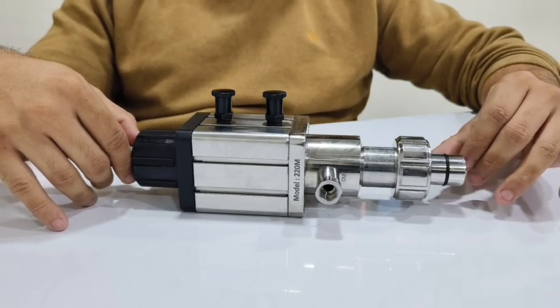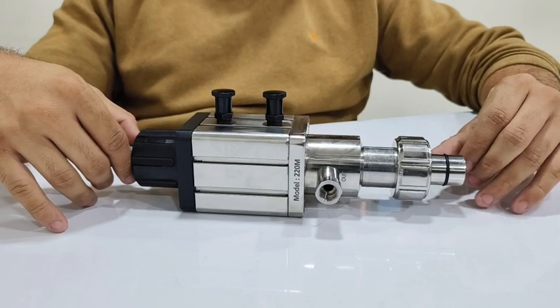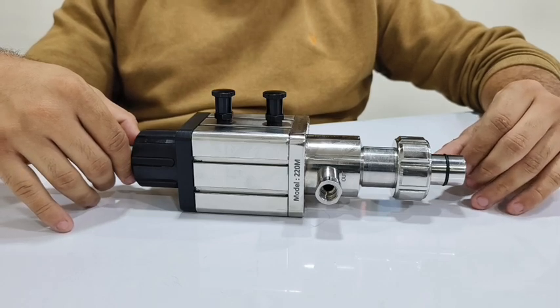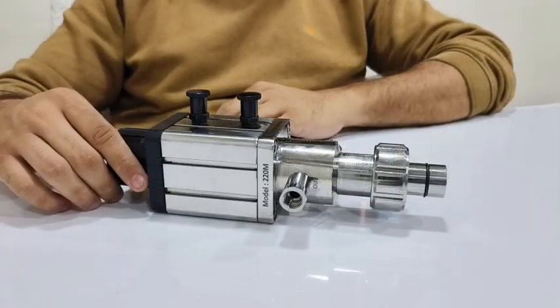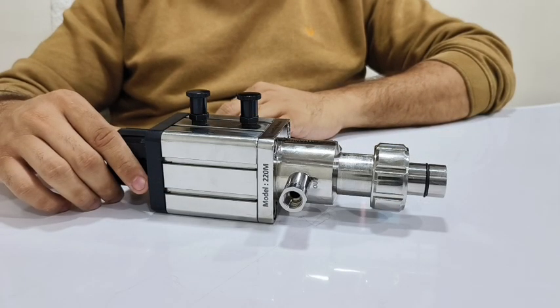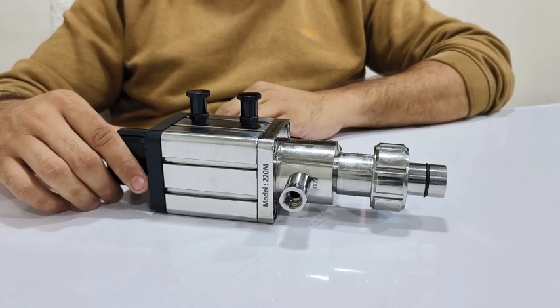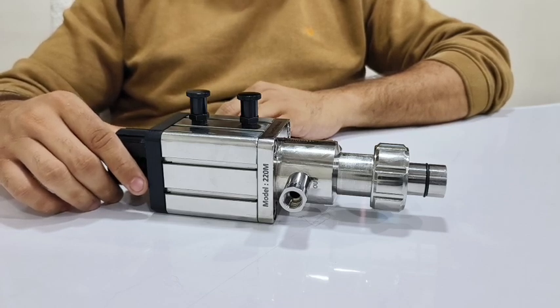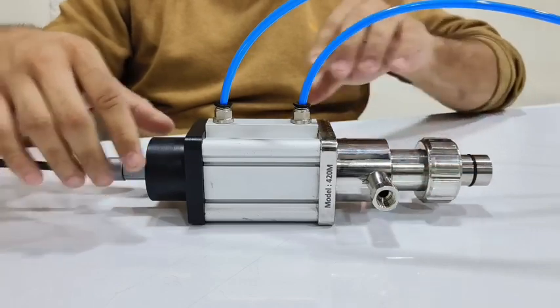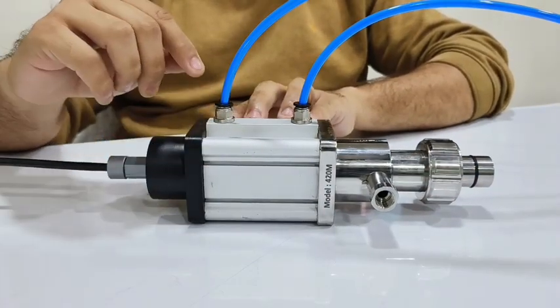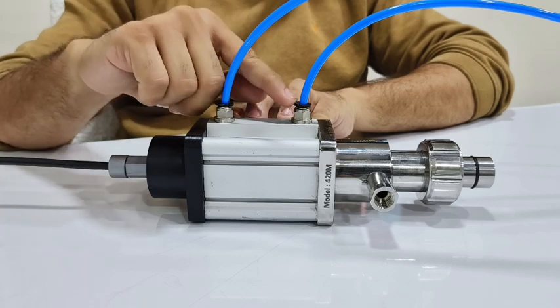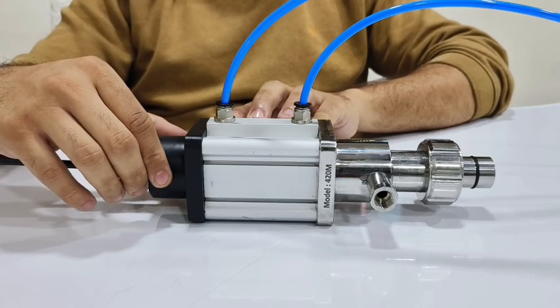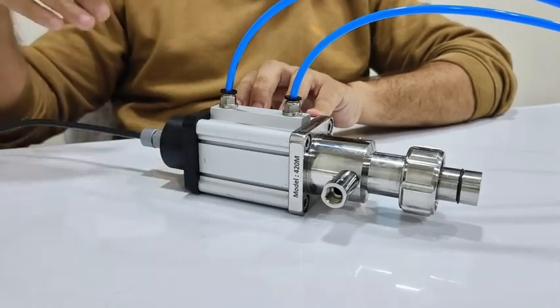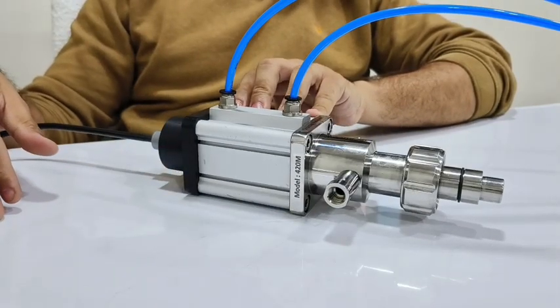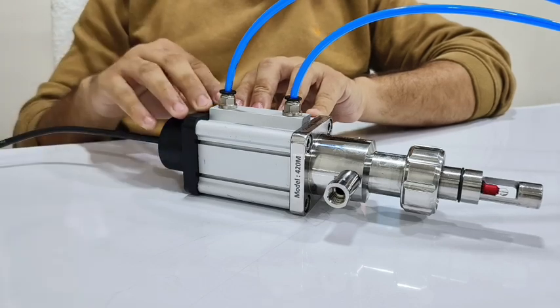Before entering the electrode back into the fermenter or bioreactor, you can perform the CIP and SIP cycles and insert the electrode back into the process. Along with the manually operated retractable electrode housing, we also offer a pneumatically operated retractable electrode housing with our pneumatically operated drive unit. In our SmartDip 420M, we have a pneumatically operated drive unit. By giving a compressed air connection in the inlet and outlet position, you can operate this remotely for your fermenters and bioreactors applications.